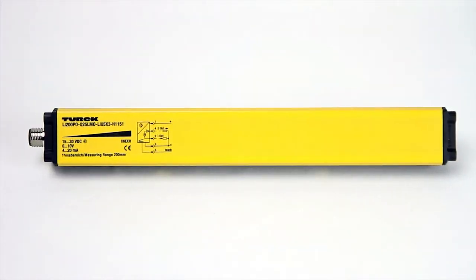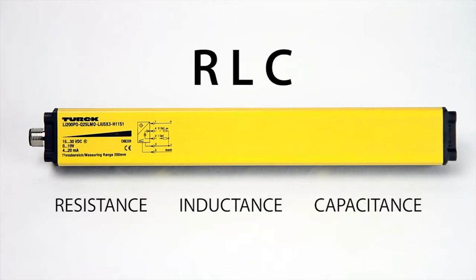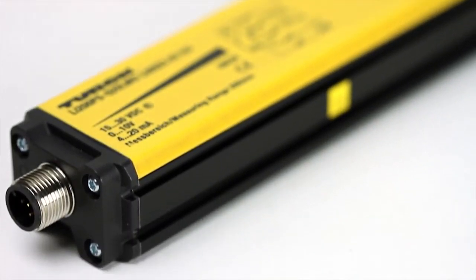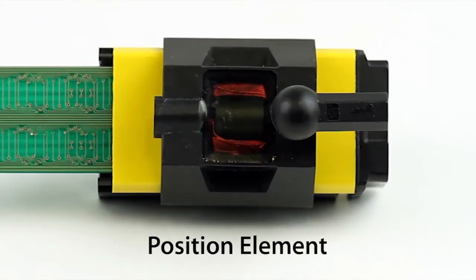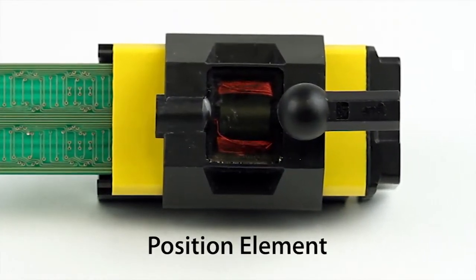One linear inductive measurement technology uses the RLC, Resistance Inductance Capacitance, principle to give more accurate and faster position feedback than ever before. This RLC circuitry makes use of emitter and receiver coils on a printed circuit board. The position element contains an inductor and a capacitor.